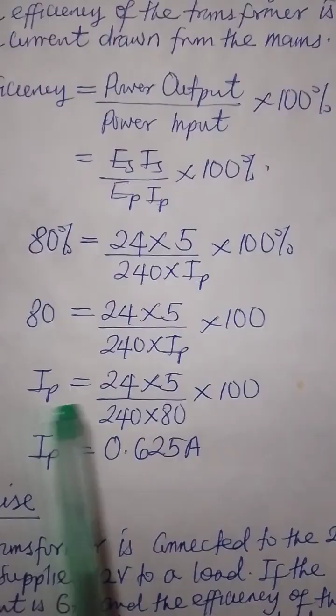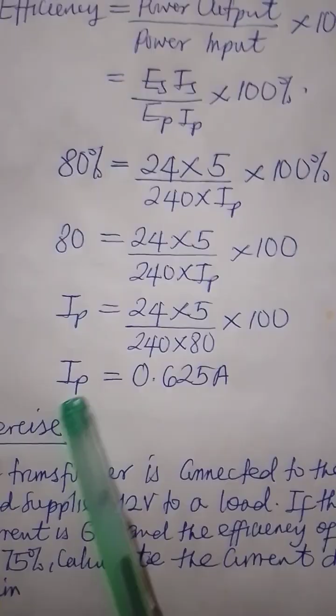Just swap position, that is, make IP subject of the formula. IP is 24 times 5 over 240 times 80 times 100. Having cancelled out the percentage, you resolve this properly, and you get IP equal to 0.625 ampere.